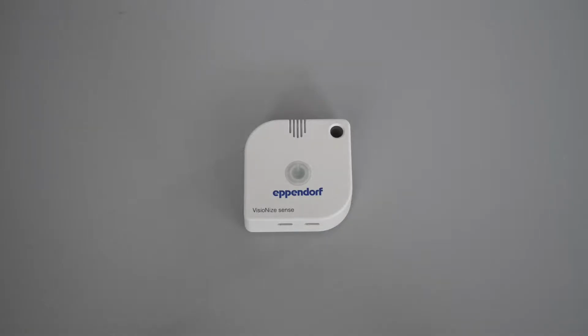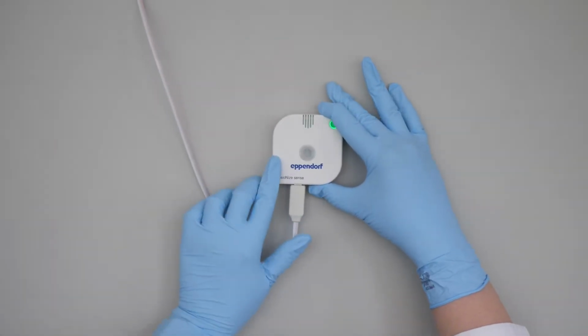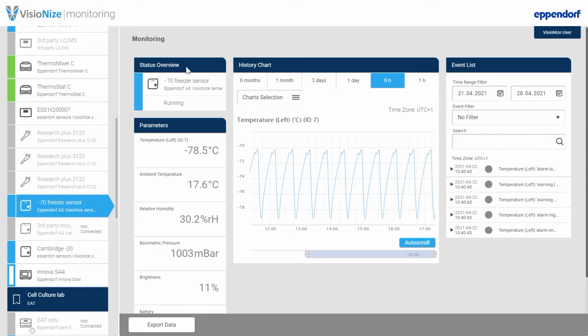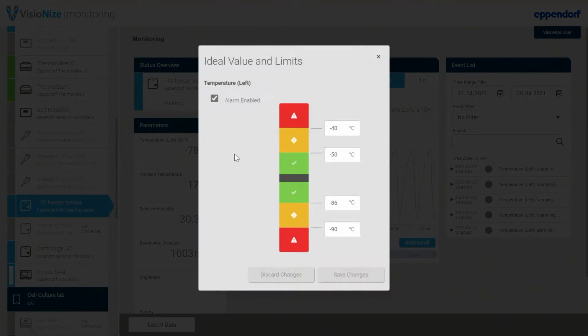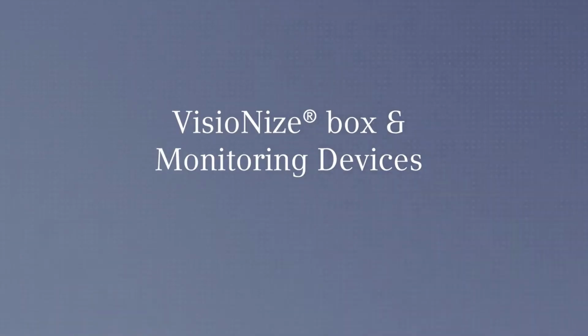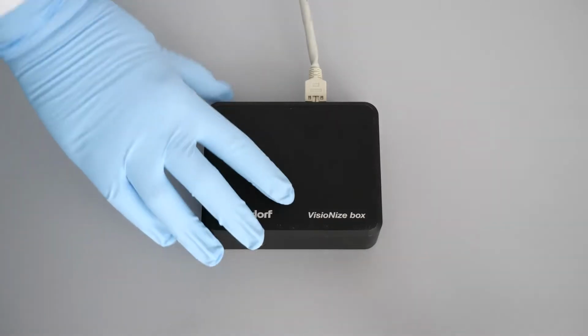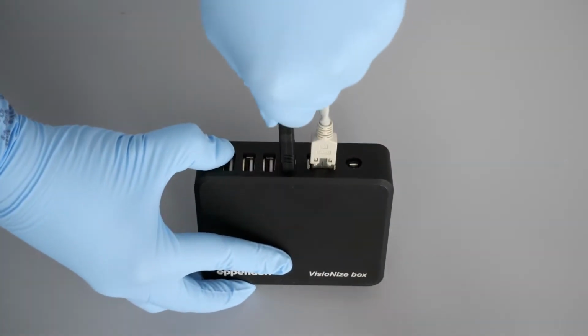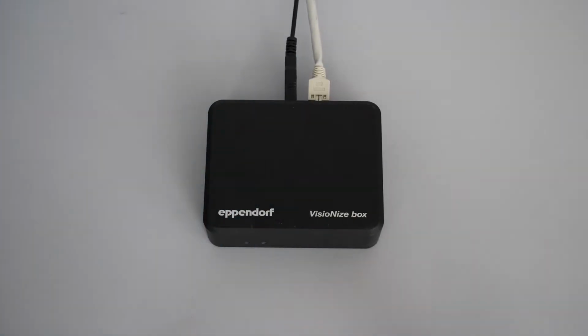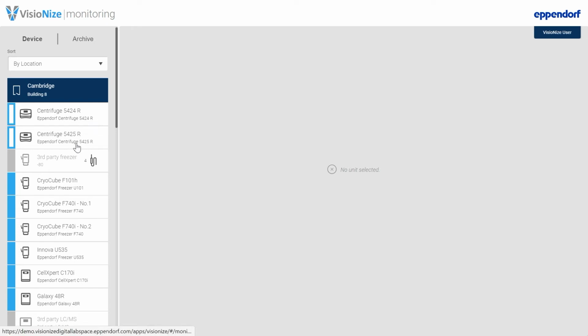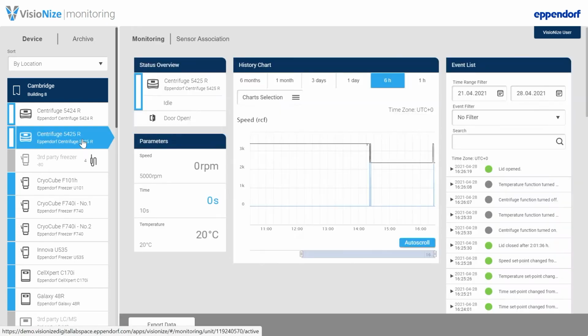With VisioNize Sense, you can monitor any temperature-controlled device. Just connect the sensor to your device. You can monitor the internal temperature, the ambient temperature, and also other parameters like relative humidity, pressure, and brightness. Just define the alarm ranges, for example, for the temperature, to receive alarm notifications. Smaller devices like centrifuges can be connected via the VisioNize box. So let's start a run at the centrifuge and let's check how VisioNize Lab Suite contributes to even smaller lab devices.